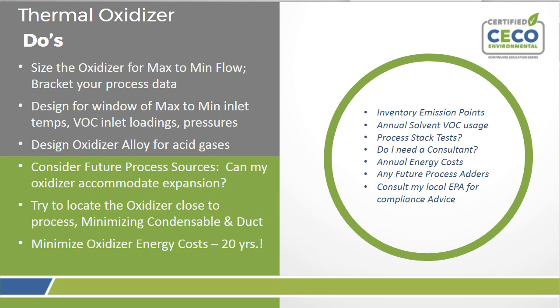Again, future expansion, this kind of goes with number one, but you definitely want to be thinking long-term. Locating the oxidizer close to the process can also be surprisingly important if possible, or you may need to manage at least the temperature of the duct. So you have a process going on at 100 degrees, but you have a long line of duct going to the oxidizer, and that gives the opportunity to cool down the process a bit and condense some of those compounds. It can pose an issue for the process fan for the oxidizer as well. But again, energy costs and plant expansion.